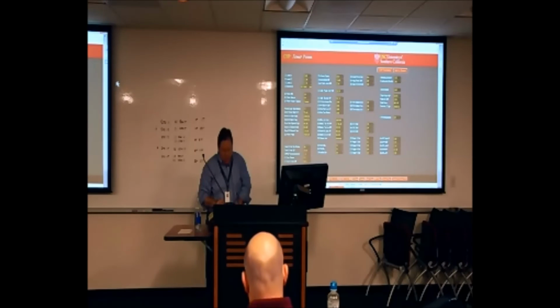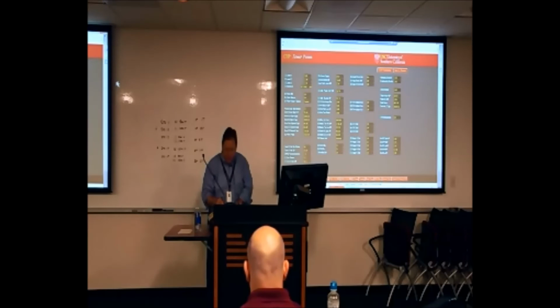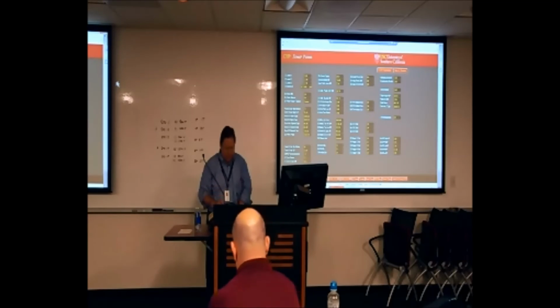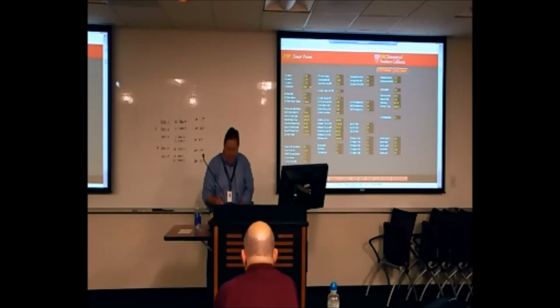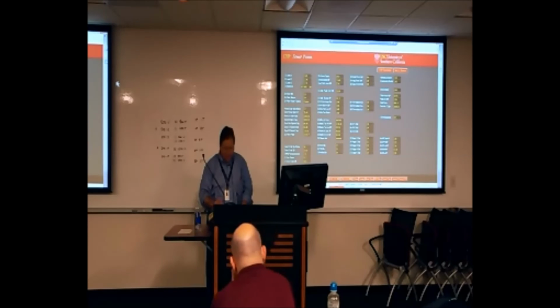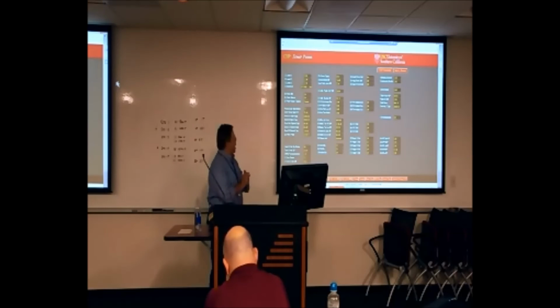There's also a fixed low limit of 65 degrees that it's never going to allow the condenser water supply temperature to drop below. There's a high limit of 85 degrees that it's not going to let it go above. So these are just fixed constraints around that reset routine to make sure we never wander below 65 or above 85. And then one other criteria comes into play.